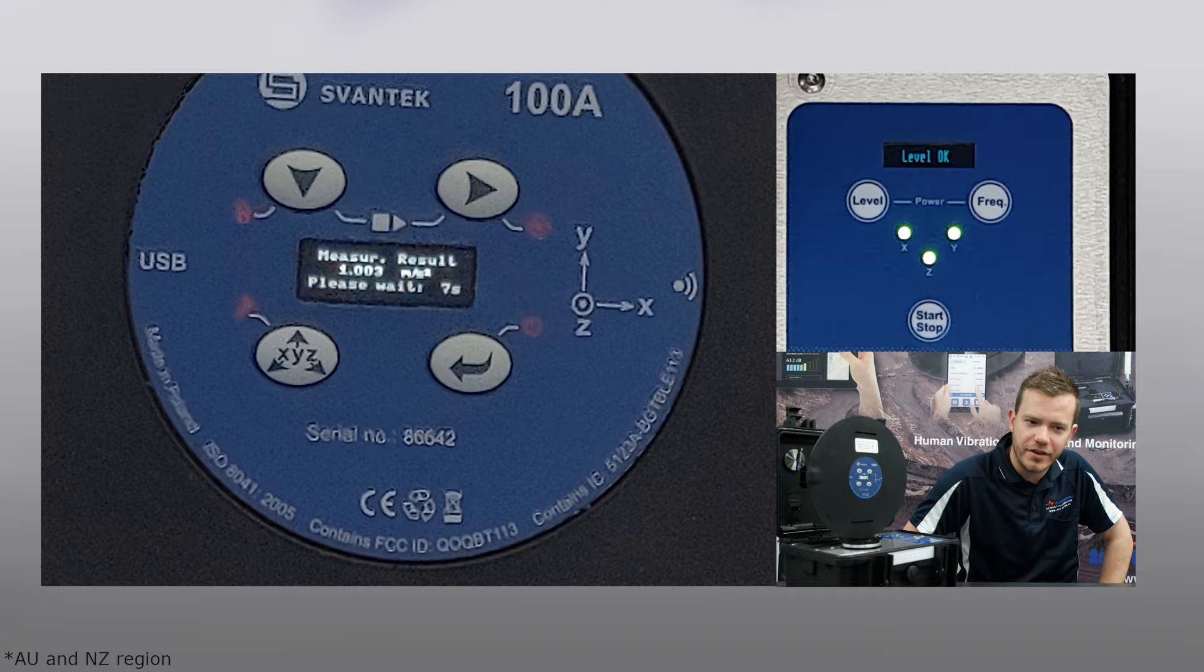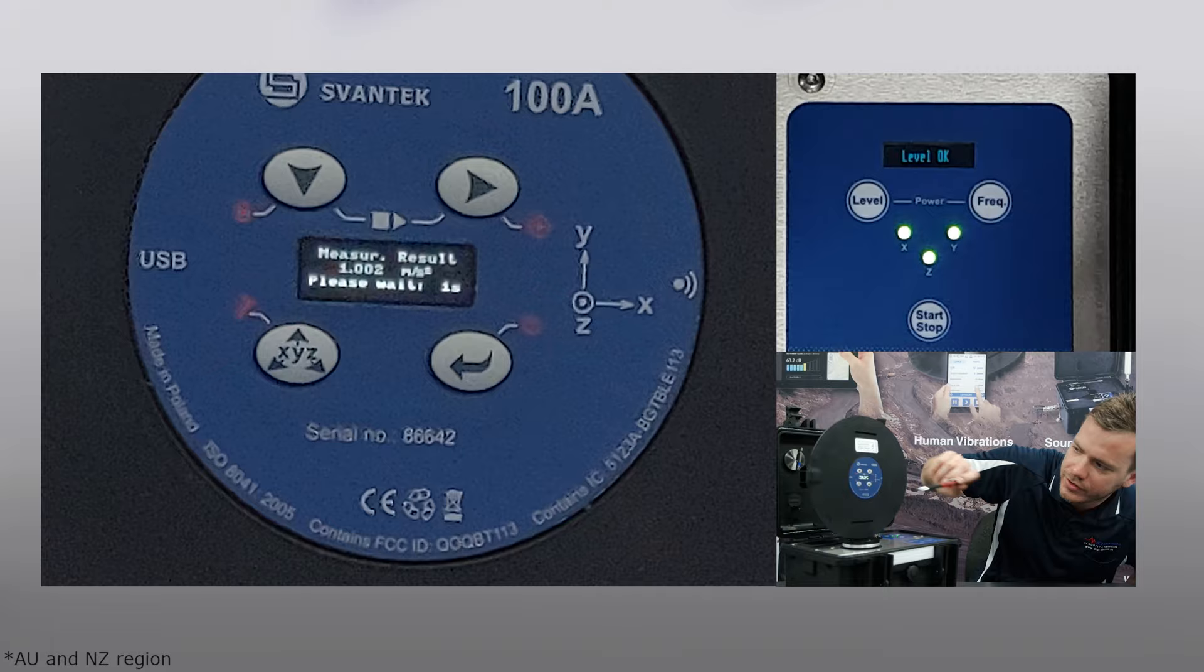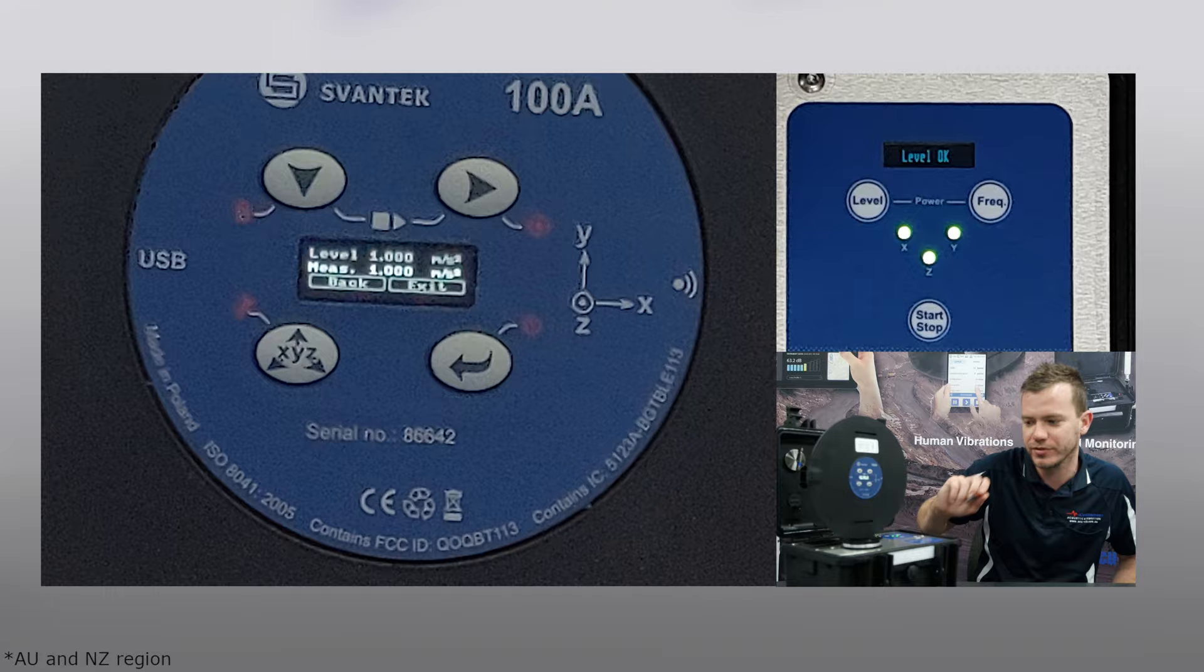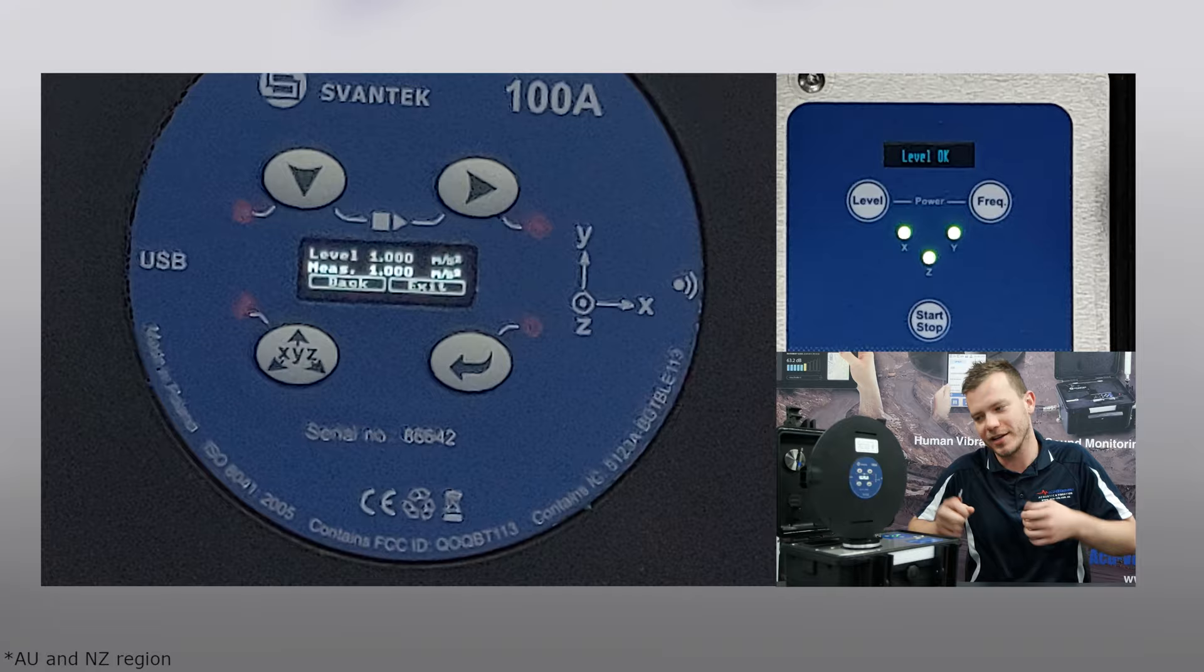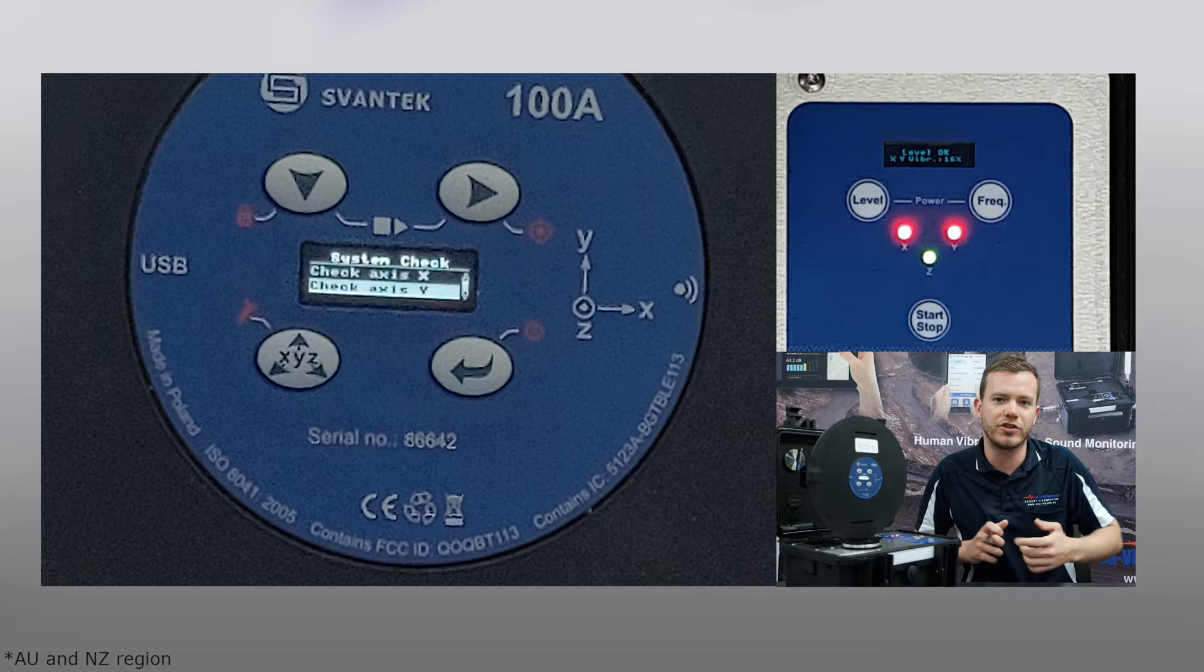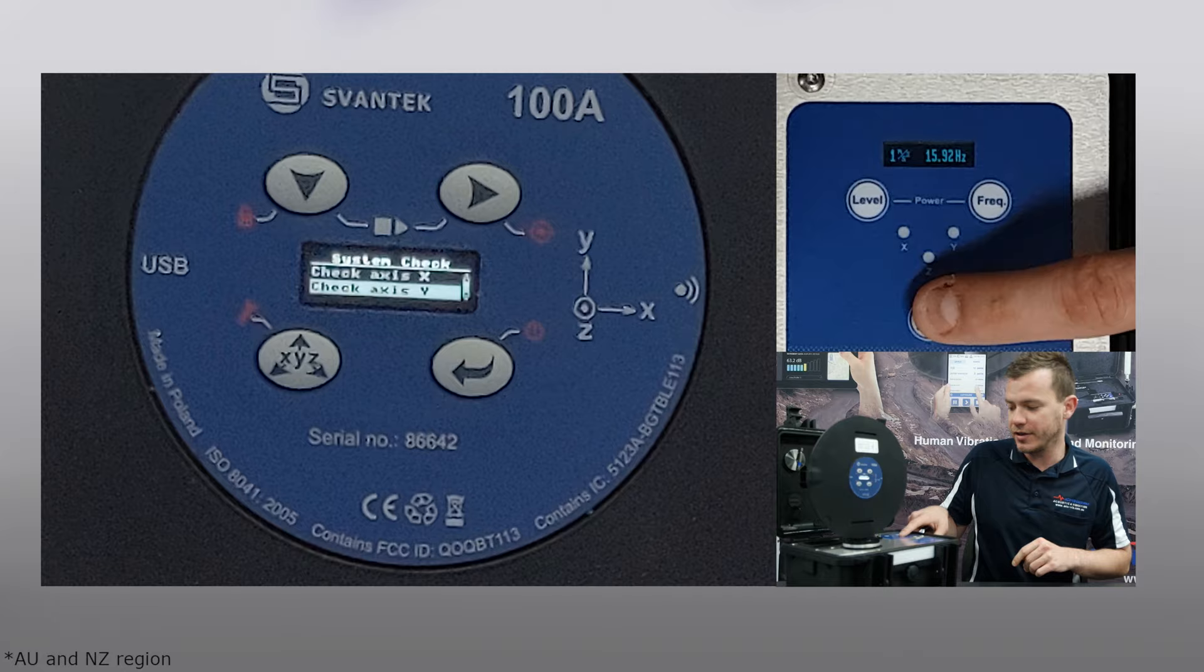We're coming to the end of our in-situ check. You can see that the level already is looking really good: 1.002. After three minutes of internal system calibration check, there's been no drift at all. That's really as good as you get. That's what you're doing before and after a measurement. If that result is out, then that's where you should technically be doing the calibration of it. Let's accept that and press exit. That'll come through in your measurement data at the end, which I'll show you through Supervisor or PC++.